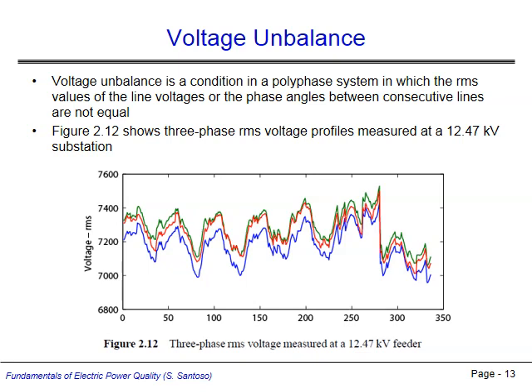During normal operation of a three-phase power system, the three voltage phases should be equal in magnitude and have phase angles 120 degrees apart from one another. This is called a balanced system. If the system becomes unbalanced, with changes in relative magnitude or phase angle between phases, power quality problems may arise if the unbalanced condition is severe enough. Voltage unbalance can be quantified in several ways. IEEE standards quantify it by the ratio of negative sequence voltage to positive sequence voltage present in the unbalanced system. The ANSI quantifies it as the ratio of maximum deviation from the three-phase average voltage to the three-phase average voltage itself.